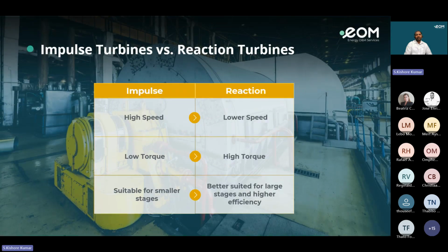Here we can see the key differences of impulse versus reaction turbines. Whereas the impulse is high speed, the reaction is lower speed. In the impulse, it is low torque; in the reaction, it is high torque. The impulse is suitable for smaller stages, whereas the reaction is better suited for larger stages and higher efficiency.